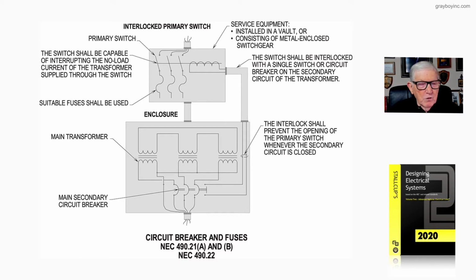Now let's read 490.21C as in car 2, title head operation. And again, let's read the last sentence of the paragraph. Unless the fuse cutouts are interlocked with the switch to prevent opening of the cutouts under load, a warning sign shall be placed at such cutouts identifying that they shall not be operated under load. Now, those are two things that we need to recognize here.